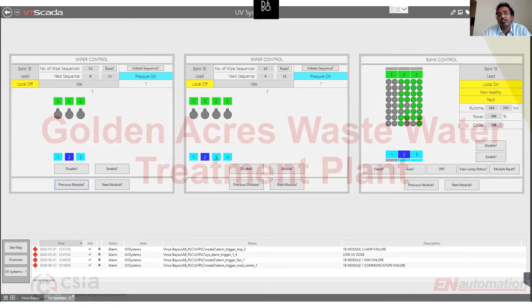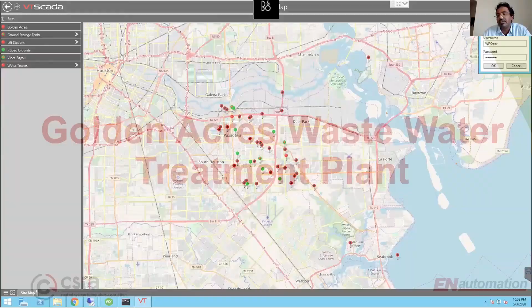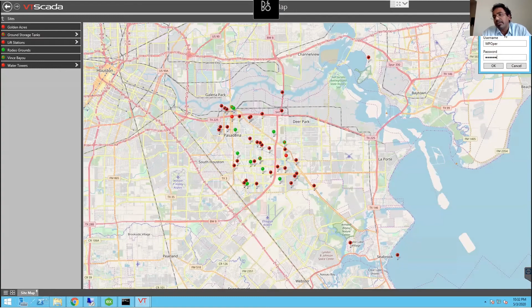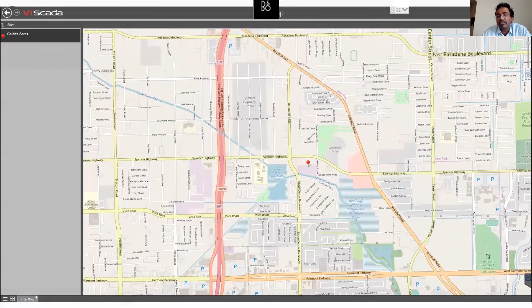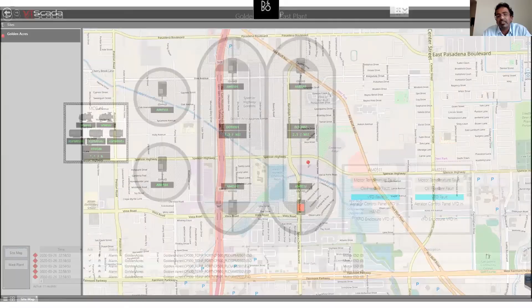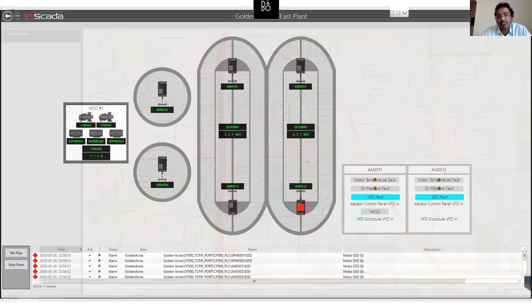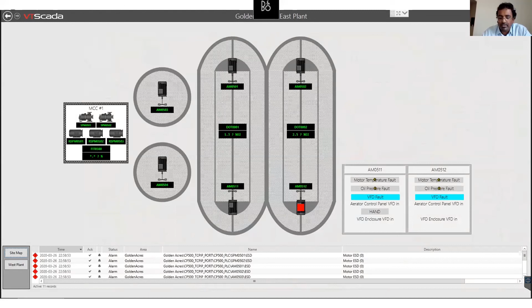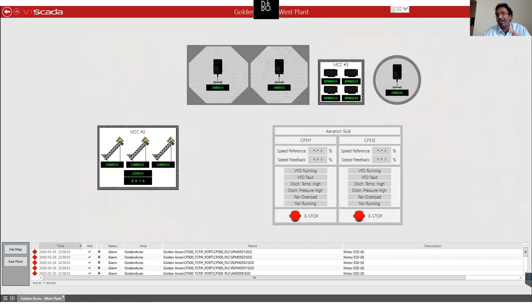Moving on to Golden Acres wastewater treatment plant, this is a plant where communication is definitely not good at the moment, and we're trying to fix it. The wastewater treatment realm is labeled GA WWTP realm for Golden Acres. The operator, who is a plant operator for Golden Acres, logs in and that's all he sees. Then he steps into the plant overview, which comprises Siemens, Legacy, and new Allen Bradley PLCs, all sending data back. The influent system, on the left side, is controlled by a SCADApack PLC, and as part of system integration we've had to bring all that information into VT SCADA.